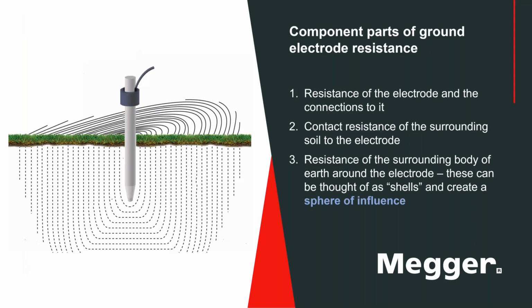Okay, let's take a look at component parts of a ground electrode resistance. Now, this shows a simple ground rod, but everything I'm going to say pertains to, if this was a quarter-acre grid, everything I'm telling you is going to pertain just the same. A ground is a ground is a ground. It doesn't make much difference if it's a rod or a large system.